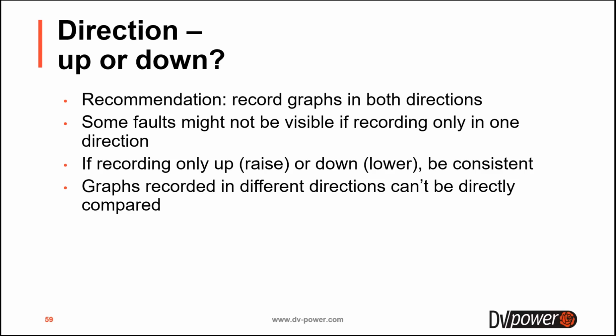Generally, our recommendation is to record graphs in both directions. This is because there are some faults that might not be visible if you record only in one direction. Also, graphs recorded in different directions can have a different look, a different layout. So graphs recorded in different directions in most cases cannot be directly compared. You will still be able to get the transition time to see the characteristic points, but you will not be able to directly compare. So it's good to record graphs in both directions.